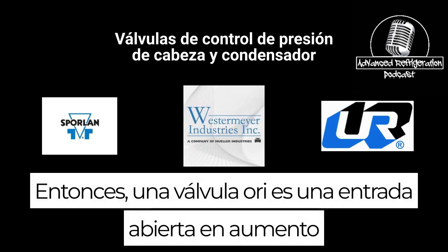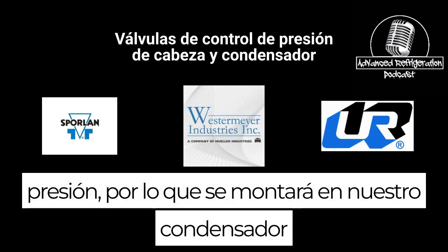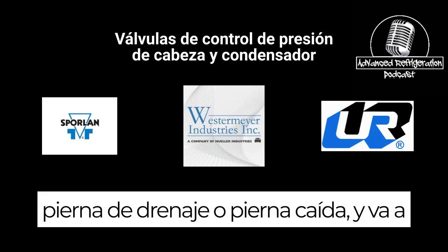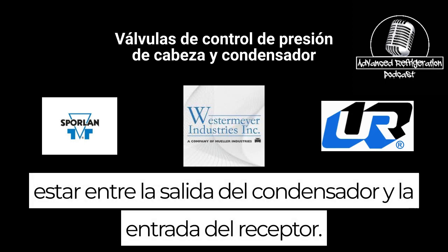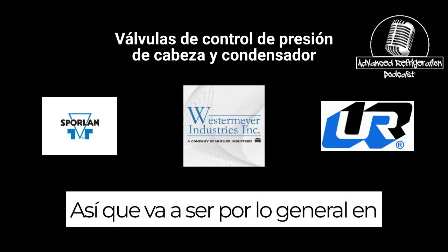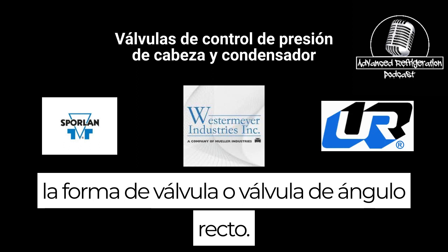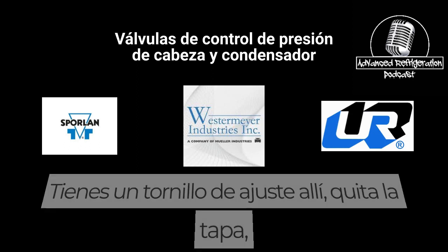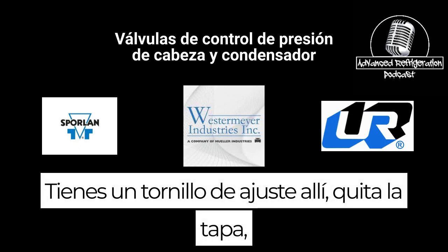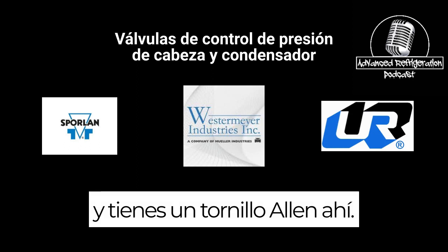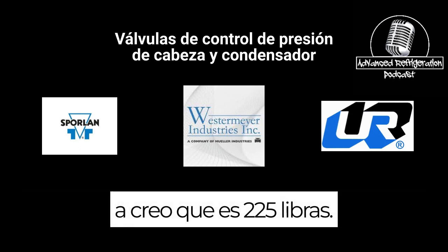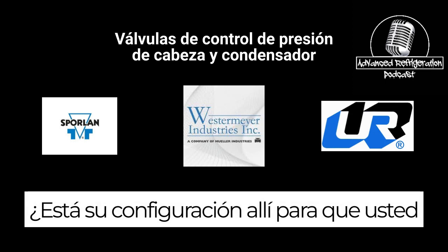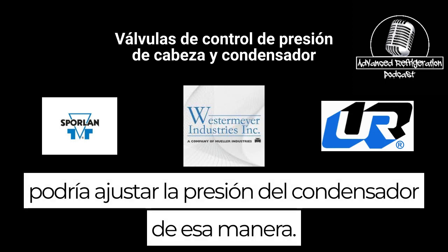An ORI valve is an open on rise inlet pressure valve. It's going to be mounted on our condenser drain leg or drop leg, in between the condenser outlet and the receiver inlet. It is usually in the shape of a right angle valve or angled valve, so it's 90 degrees. You have an adjustment screw on there, it'll cap off, and you have an Allen screw on there. The setting can be anywhere from 0 to 225 pounds, so you could adjust your condenser pressure that way.